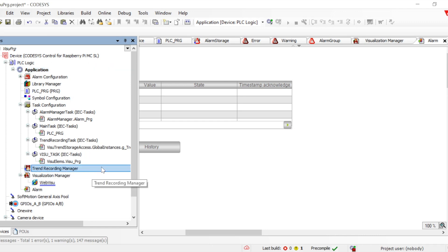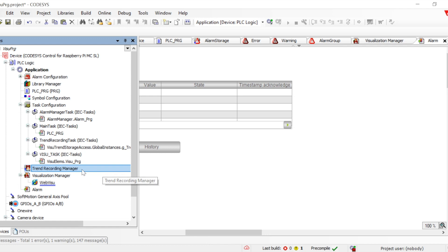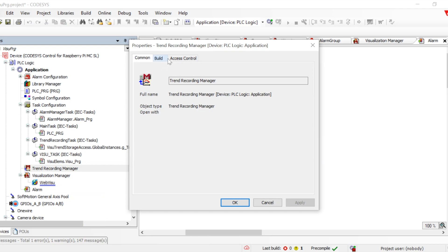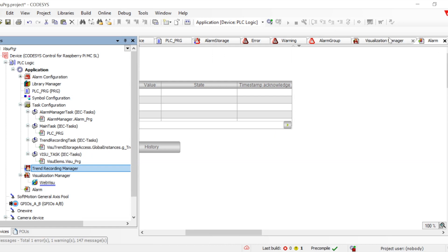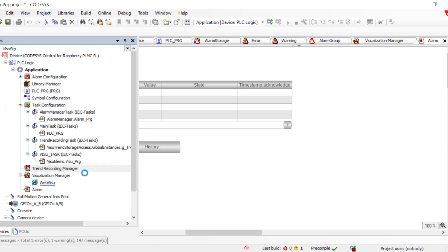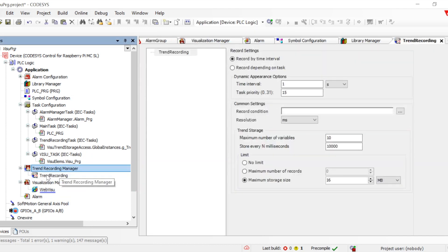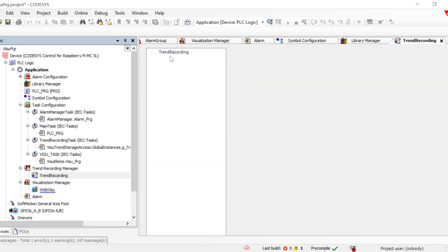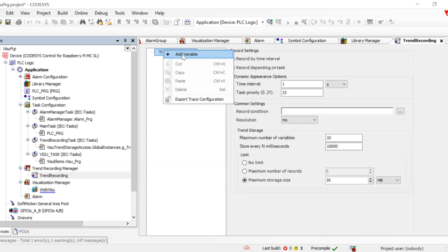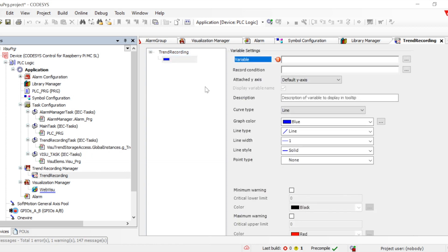This will help us to create new trends. We can double-click on it, but it won't give anything because we need to right-click first — that will give us the options. We can check out the properties; it has the same common build and access control. Now right-click on it, go to Add Object, then Trend Recording. We can give it a name or keep the default. Once the trend recording is added, all properties get populated on the right side, and we can right-click there and click Add Variables — this is how a variable can be added into the trend recording.